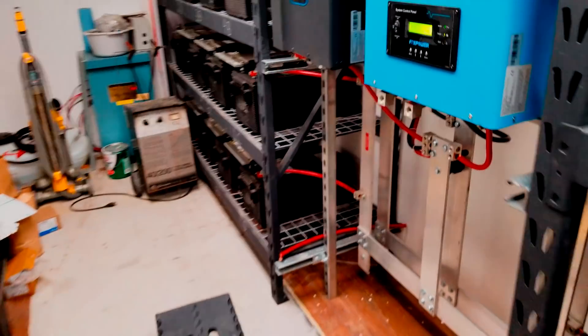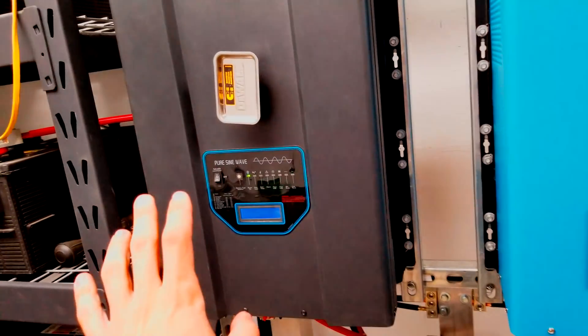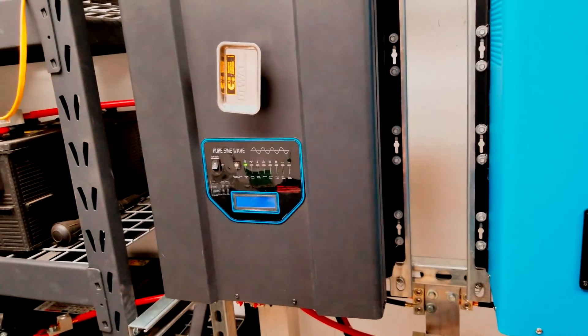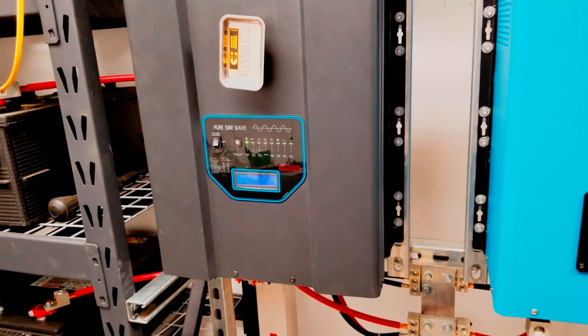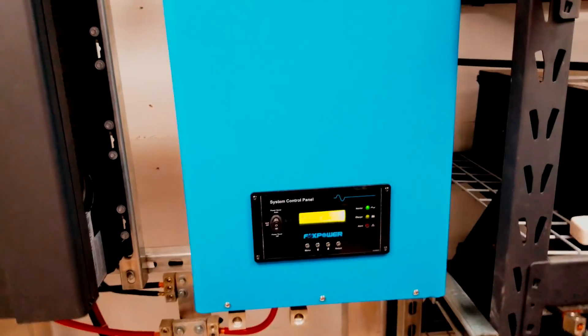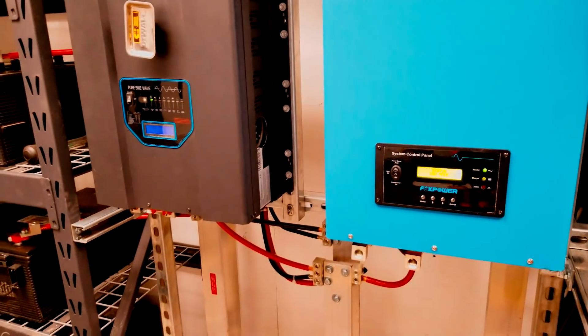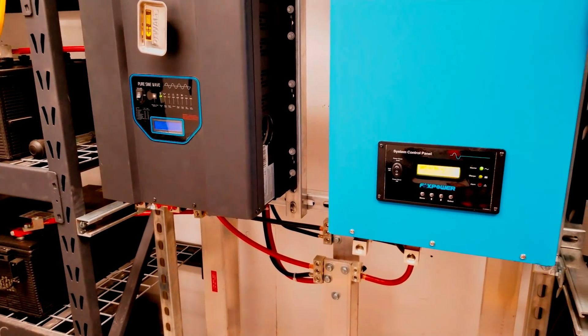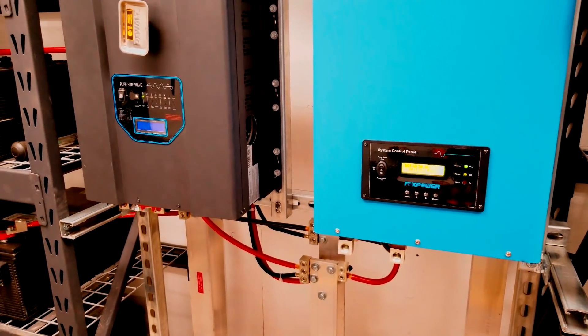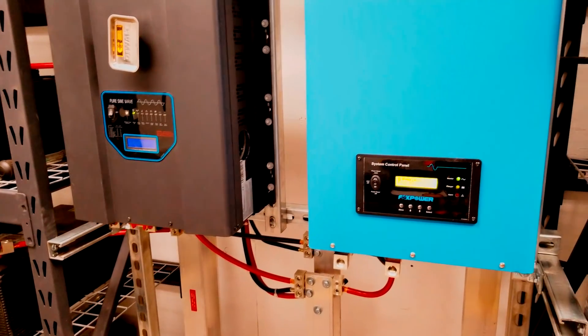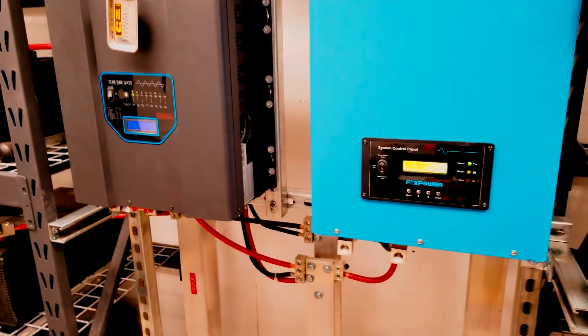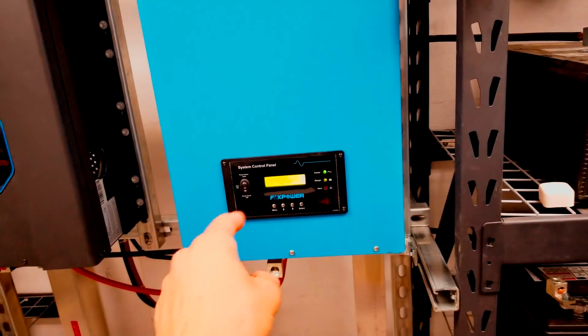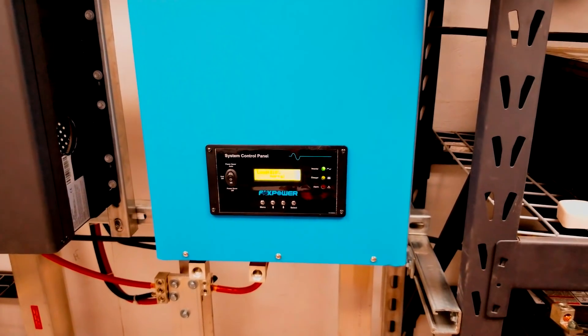So when the generator is running, I can pick and choose which inverter I want to use as the battery charger. And what that allows me to do is that allows me to use this inverter as the battery charger, and it'll pull about 30 amps on the generator. And instead of then having the reduced capacity on the generator, because it's a 14 kilowatt generator, instead of only having, you know, six or seven kilowatts left over to run the rest of the loads...